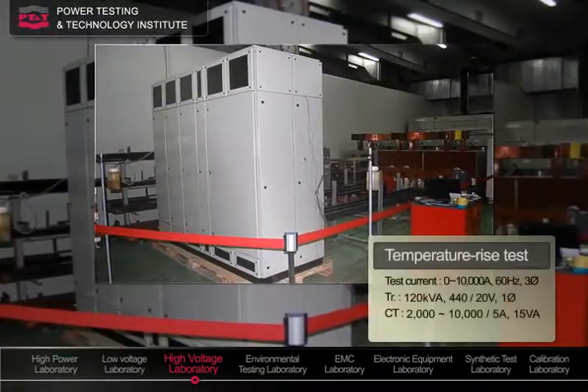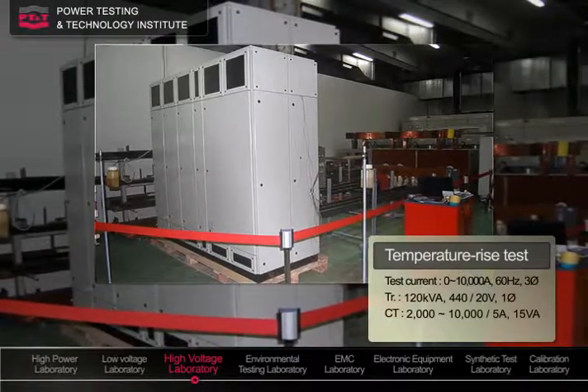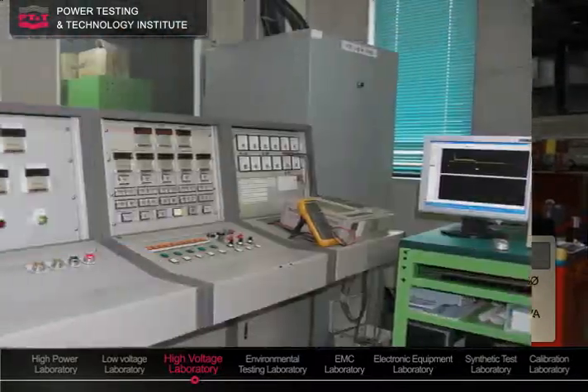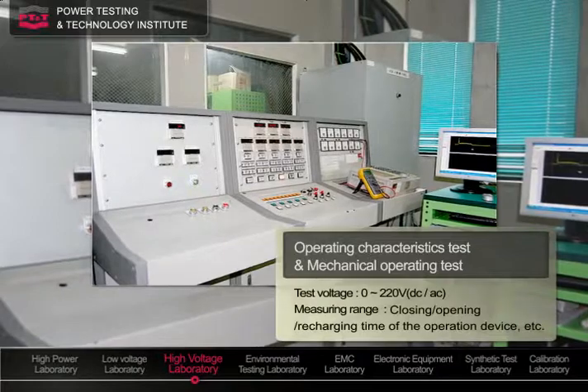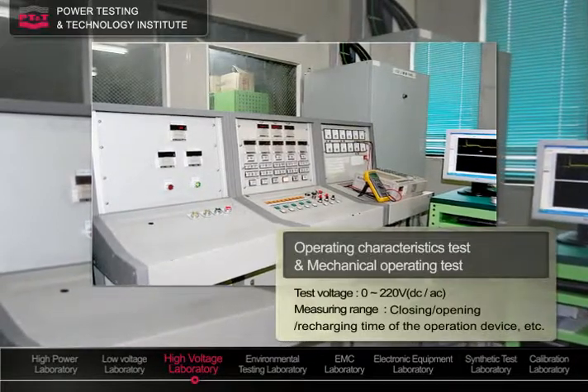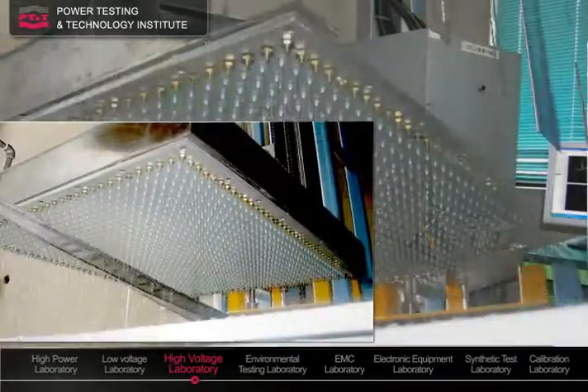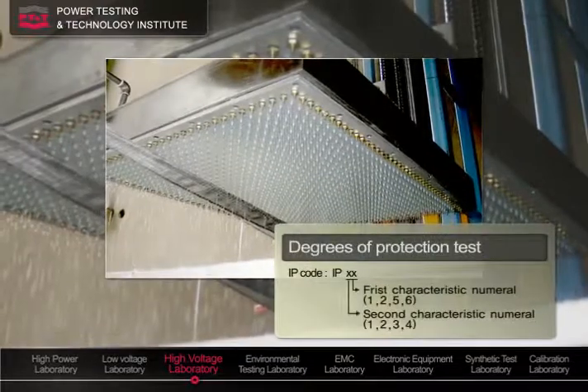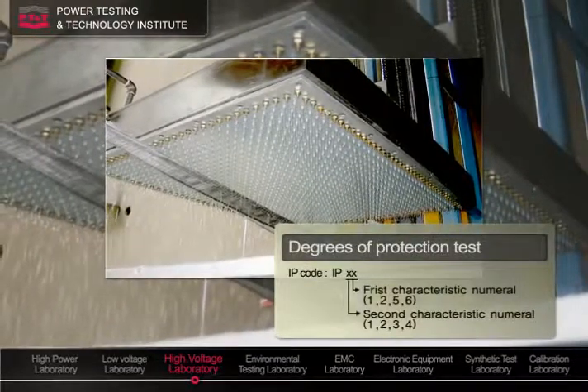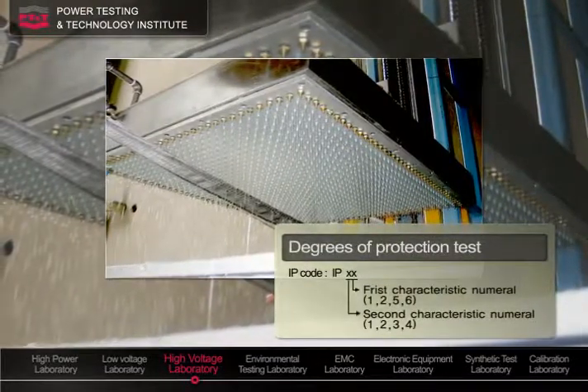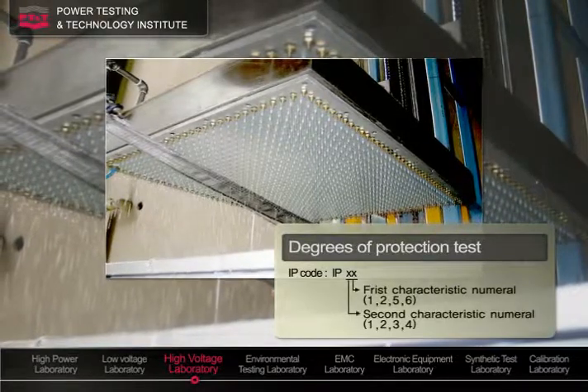Current carrying performances are verified through temperature rise tests. Lifelong durability is evaluated with electrical and mechanical operating tests. Furthermore, water and dust tightness of enclosures are tested to determine protection class.